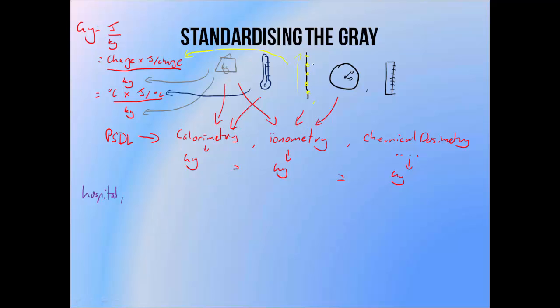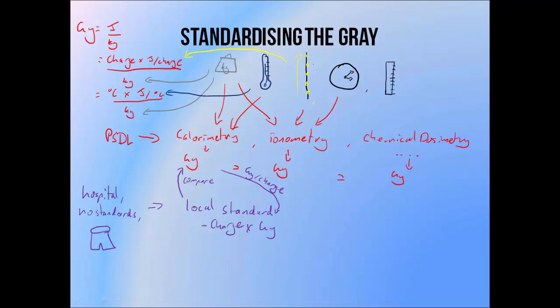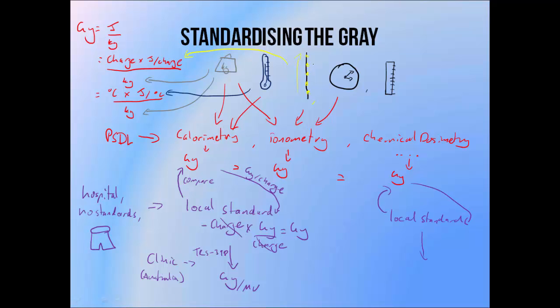In the actual hospitals themselves, performing measurements of this many quantities with this sort of precision isn't practical. So what we do instead is something similar to the method of pants calibration discussed earlier. We send our local standard, which is an ionisation chamber that is only able to measure charge, to a standards lab. The standards lab will measure out a known dose of radiation in terms of grey, and compare the number of grey delivered with the measured charge. This ratio of grey per measured charge is called a calibration factor. It can be used in the hospitals to obtain measurements in terms of grey. We use the calibration factor in conjunction with a dosimetry protocol like TRS398 in order to obtain these measurements. The code of practice allows us to apply a calibration factor determined in a particular beam at the standards lab to our own potentially vastly different clinical beams. Every treatment centre should have an ionisation chamber with a calibration factor that is traceable to a primary standards dosimetry laboratory. Because these chambers are calibrated at standards labs that produce the same value of grey around the world, we should all be able to obtain the same value of the grey in our own clinics as well.